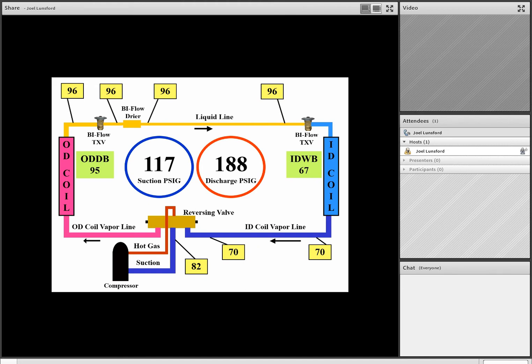And sure enough, that's our diagnosis. As you take a look at the screen, a leaking reversing valve with high suction and low discharge pressure and a large temperature difference across the two cool lines. Well, team, at this time, let's continue with some service calls.